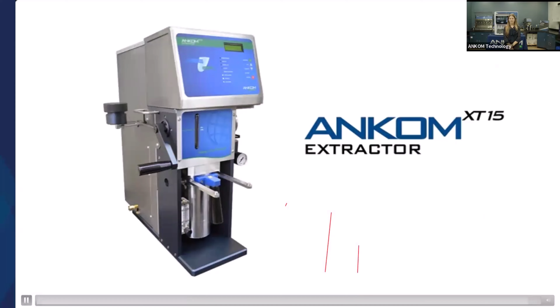So as you can see, the XT15 instrument operates very similarly to our Delta fiber analyzer in the sense that the technician really just needs to have proper weighing skills for their sample, and for diatomaceous earth, if that's needed in the method, to weigh into their filter bags. They place their filter bags in the instrument, and then the instrument does the work. So the technician's able to walk away while the XT15 is extracting your crude fat or while the Delta is extracting your fiber components. And when they come back, they will dry their filter bags and get their final weight. So both use indirect methods and the values are found gravimetrically.